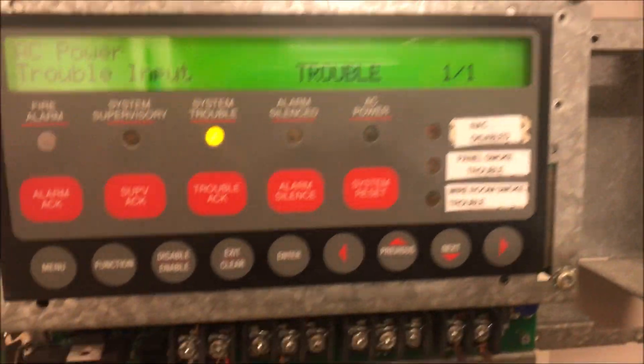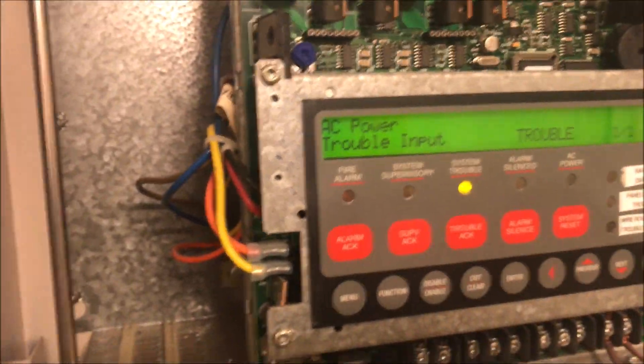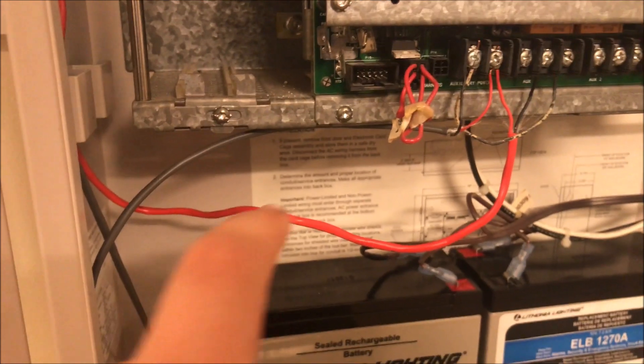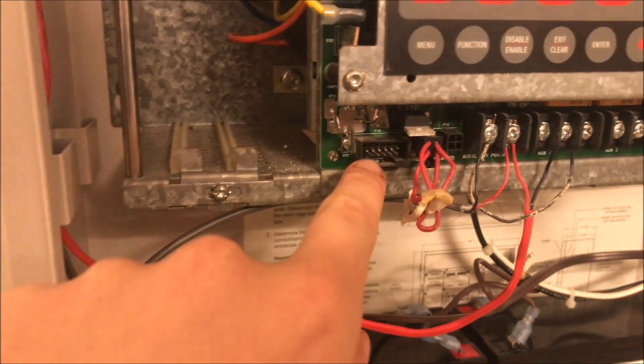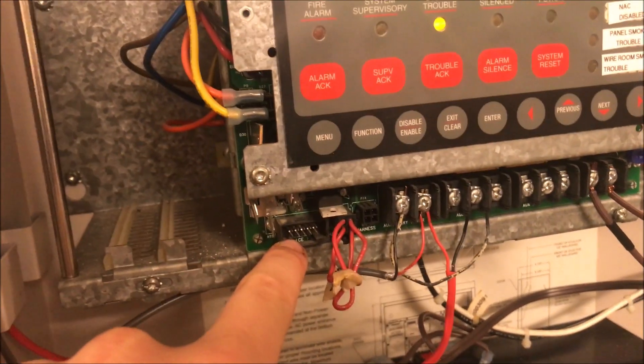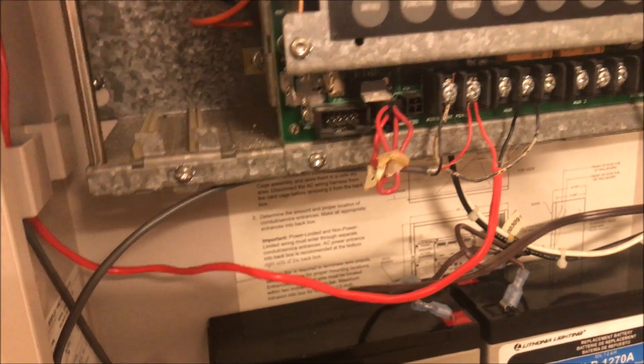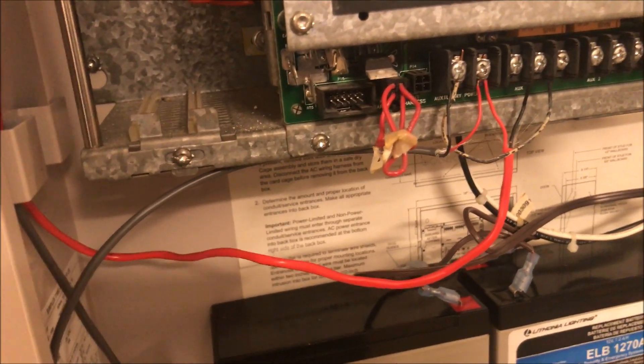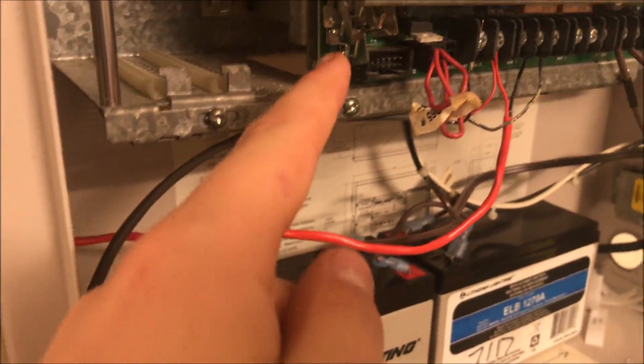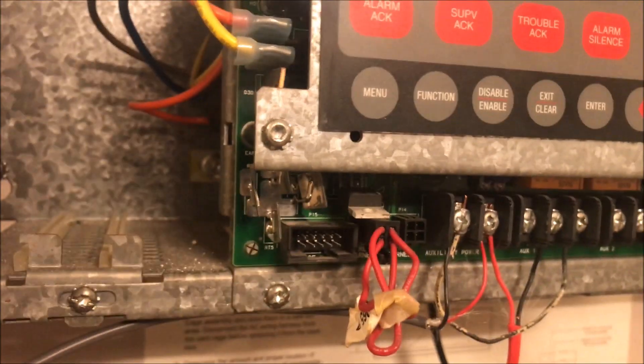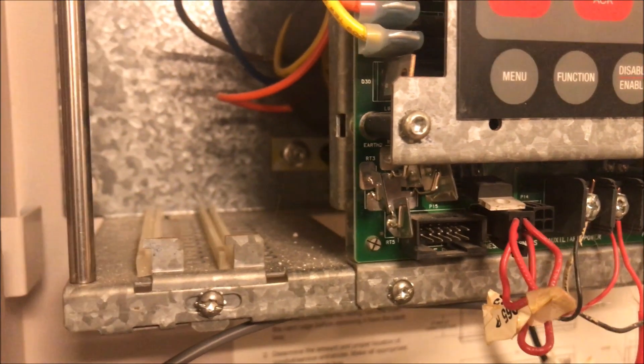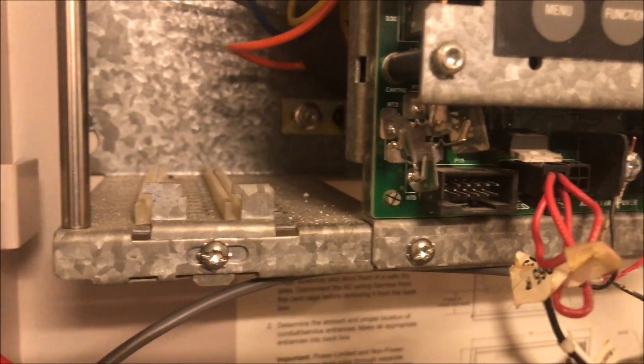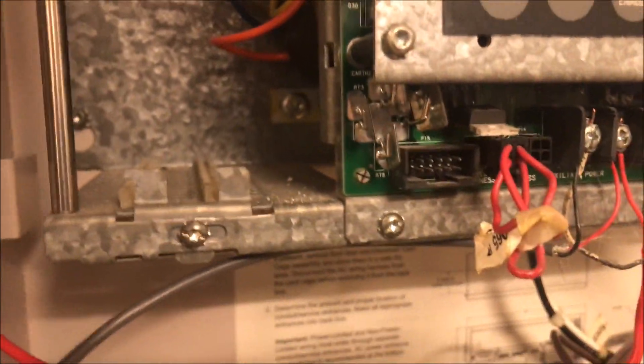The rest of this is stuff that's already pre-wired. You don't have to mess with any of these wires. There's this port labeled 'service port'—if you have a Simplex serial cable, you can program the panel through a computer here. Never ever touch these four silver discs, and never let them touch anything metal. Those are thermal resistors on the panel to make sure it doesn't overheat. If it does, it will shut down the panel, so be very careful.